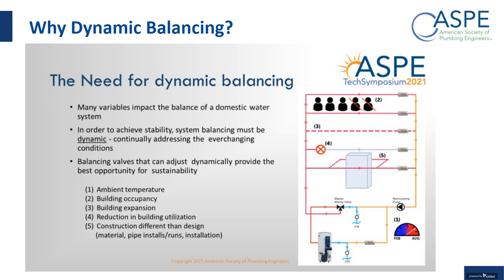We've had situations, especially when I've seen some of the hotels where they did expansion, and now they basically would have to rebalance the whole system based on expansion. With thermostatic balancing valves, you don't have to worry about that. Once the system is balanced, they will all basically act independently of each other and adjust the flow where they need to offset the heat loss.